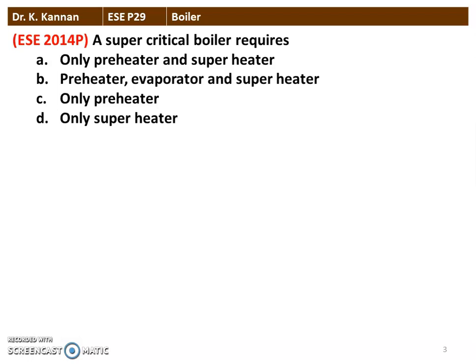Next question: a supercritical boiler requires — options are: only preheater and the superheater; preheater, evaporator, and the superheater; only preheater; only superheater. The supercritical boiler operates above the critical pressure, so it requires only the preheater (water preheater, known as economizer) and the superheater. We have economizer and the superheater in the supercritical boiler, where the operating pressure is above 221 or 230 bar.